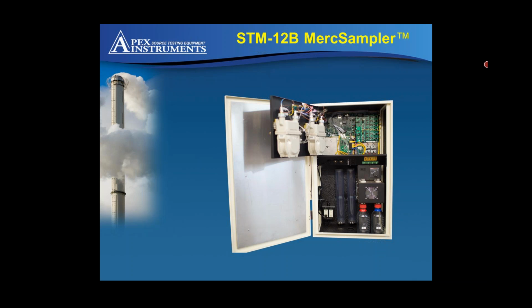Okay. We have this thing at Ericsson sometimes when it starts up and during load changes where there's some swirling or something and the flow monitor pegs out and they have to play with the fans to get it to read well. We just had one of those incidents that lasted like 8 hours. So I don't want it to be tied to a number that's not accurate at all.